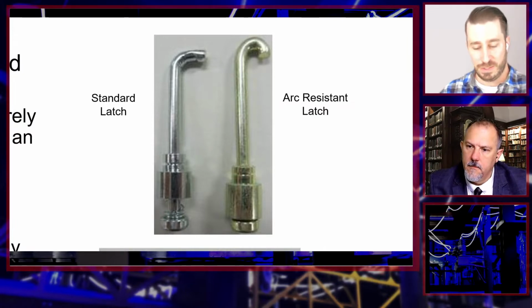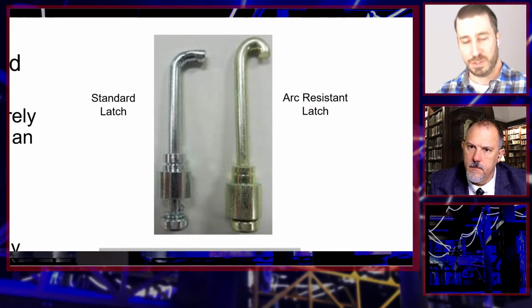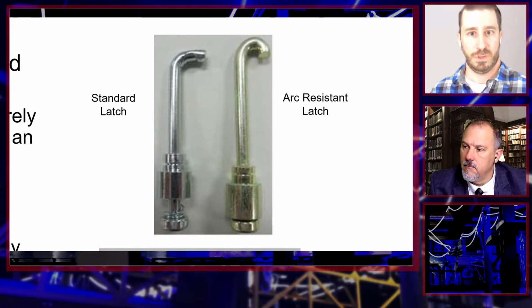Interestingly, the latches have a spring there, and during the actual event, that spring helps burp the equipment, if you will, from some of the pressure buildup. Obviously not letting out a significant amount of energy, but enough that the equipment's still performing.